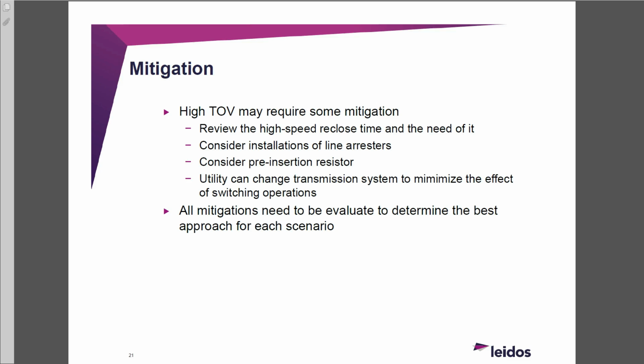So then he starts saying, well, I'm at 50% of the line and I still have terrible TOV, so he starts looking at more lines, opening it up. But if he's at that long line, we're not just picking one. If you have like 30 lines, we're doing at least 10% across various regions, benchmarking it back and back. I would not recommend just doing one, we do a couple, like a couple of loops. Doing a lot is a lot of work.